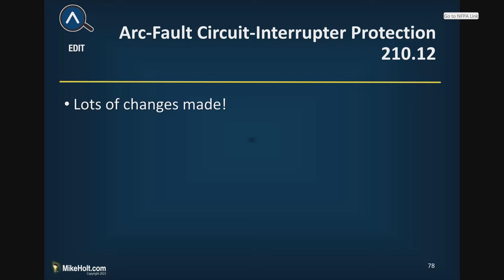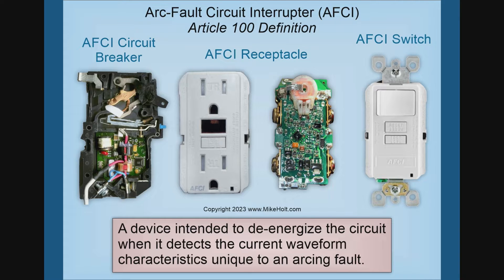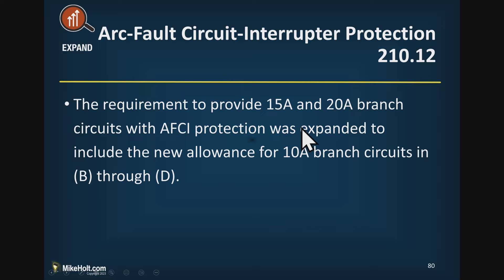Arc fault circuit interrupter protection — 210.12 — has lots of changes. We discussed this previously when it had to do with protection against hazards. AFCIs can come as electronic devices, as a circuit breaker, or as a receptacle. The requirements to provide 15 and 20 amp branch circuits with AFCI protection was expanded to include a new allowance for 10 amp branch circuits.